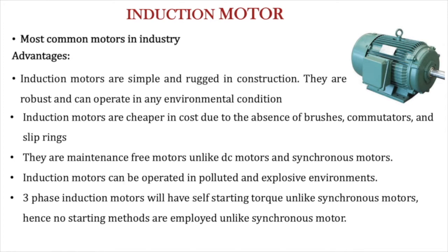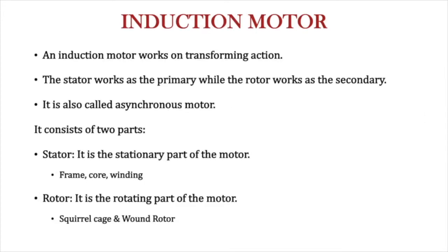DC motors and synchronous motors have the commutator and brush arrangement, so they need frequent maintenance. Induction motors can be operated in polluted and explosive environments also. Three-phase induction motors have self-starting torque, unlike the synchronous motors, hence no starting methods are employed unlike the synchronous motor.